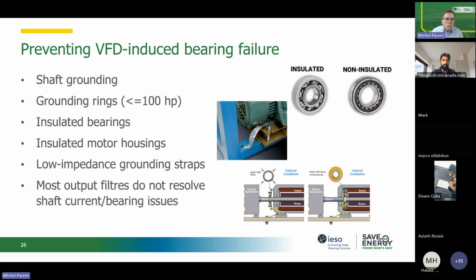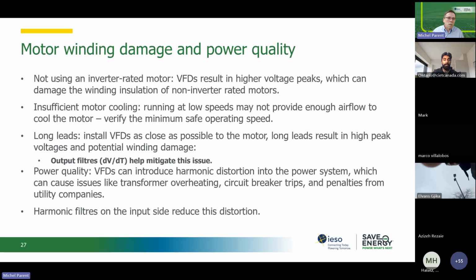There are different ways of resolving that, but if you have repeated bearing failure after the installation of VFDs, it is because of this VFD-induced current in your bearing, and you need to resolve that by proper grounding of the shaft. Like I said, you can look at those grounding rings, those low impedance grounding straps that you see in the picture here. There are different ways to do it, but you need to make sure that the current that builds up because of the VFD in the shaft will be grounded.